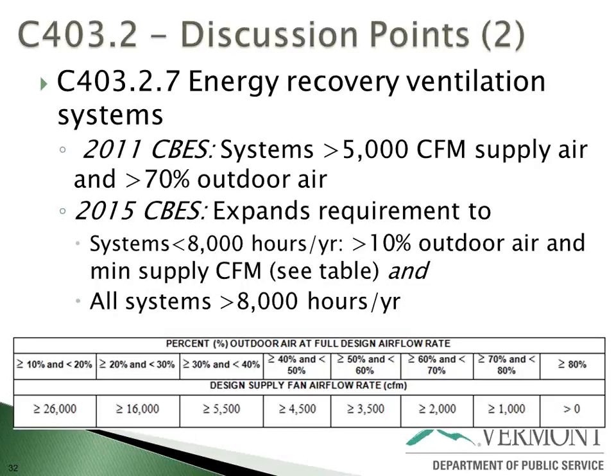So there's a lot of numbers on this slide. In general, what we have now in Vermont is if your system has 5,000 CFM supply air and it's taking in at least 70% outdoor air, then you're required to do energy recovery on that ventilation system. The new proposal would expand that pretty far down. So if you have anywhere over 10% outdoor air and a big level of CFM, that far left on the slide here, 26,000, you would need to have energy recovery. So essentially, hitting more systems.